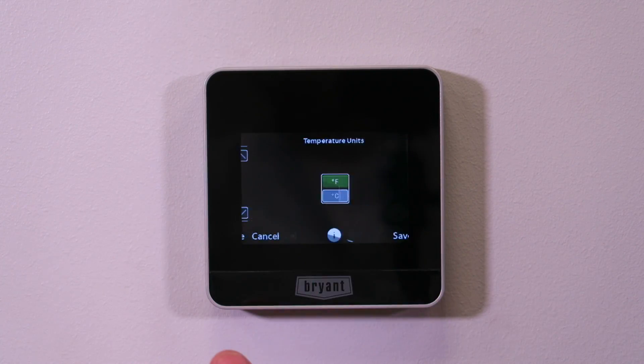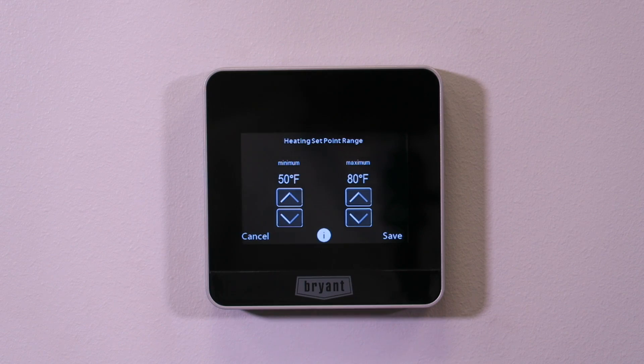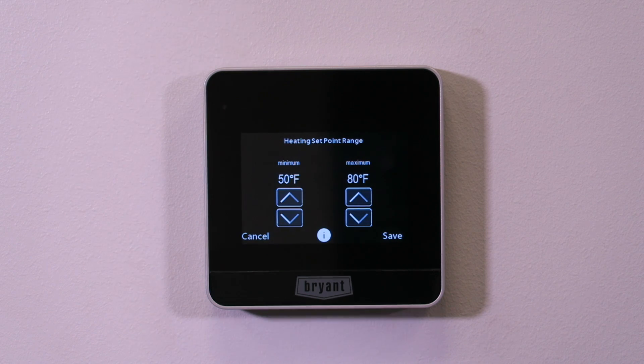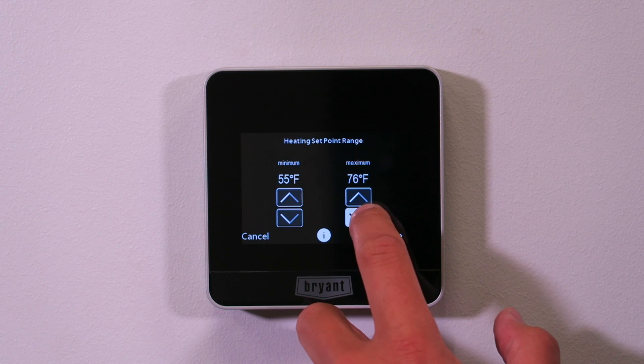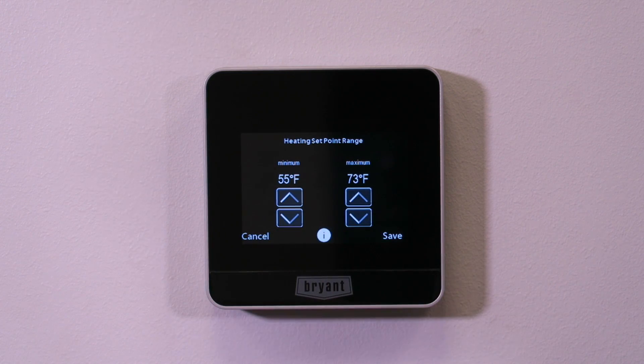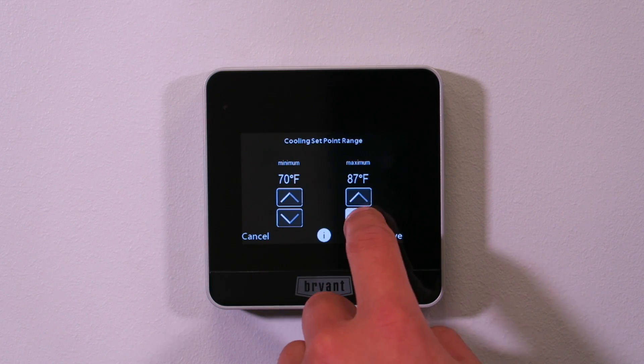Temperature display covers Fahrenheit and Celsius, which we did during basic config. Heat set point range lets you set the lowest and highest heating set points — 50 and 80 are the defaults. Maybe you want to bump the minimum to 55 or prevent your family from raising it above 72 or 75; once set, the user cannot go outside that range. Hit save. Same thing on the cooling side — pick your lowest and highest, maybe 70 to 85, and save.